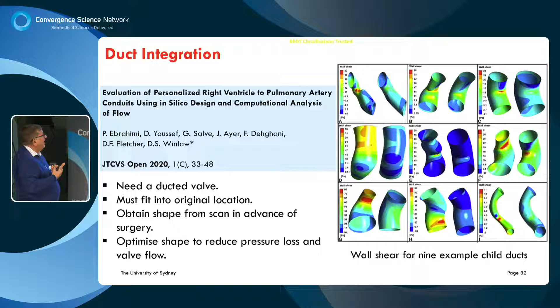So on the left of each of those pictures is a scanned conduit, and on the right is basically done a bit of optimization to remove kinks in that, to start to think about where you'd put the valve in this. Because again, you can't just test a valve in a perfect pulse duplicator with a straight tube when it's going to have to go into this tight duct, because you might start getting flow separations that you're not aware of. So you've got to be able to move forward and use your models in these complex situations.